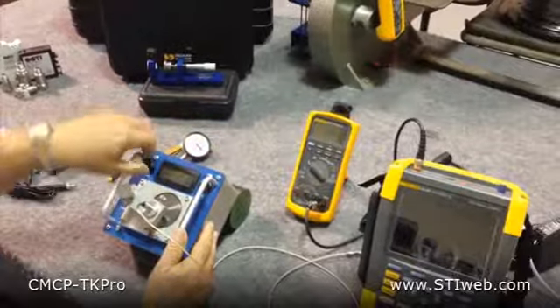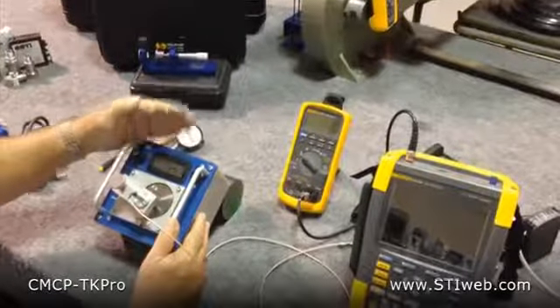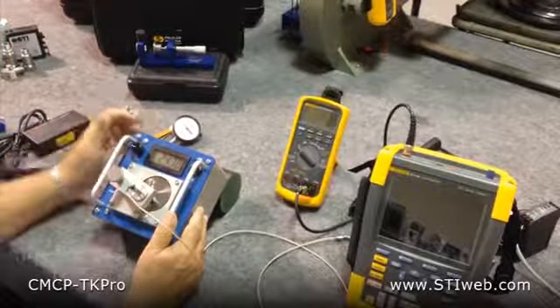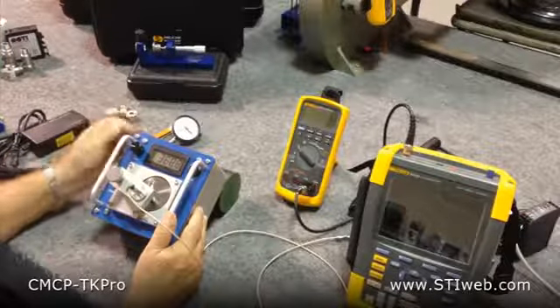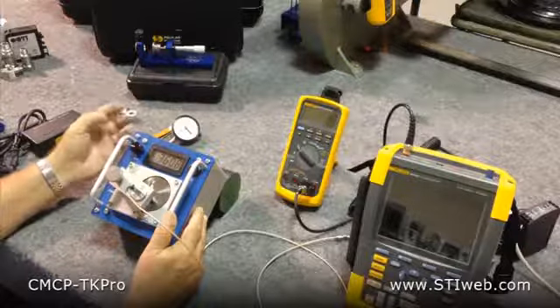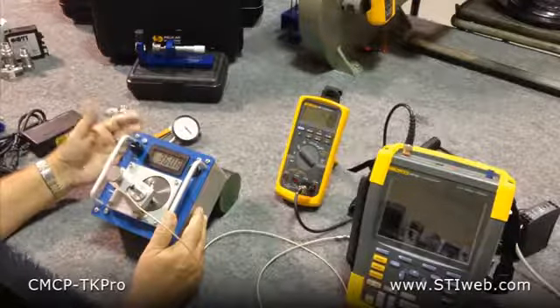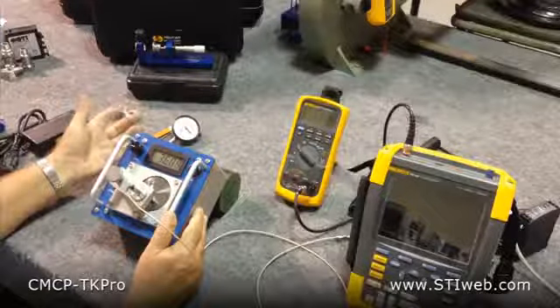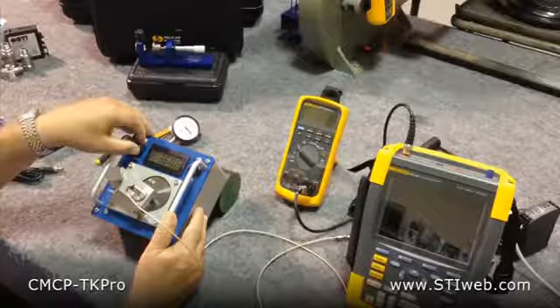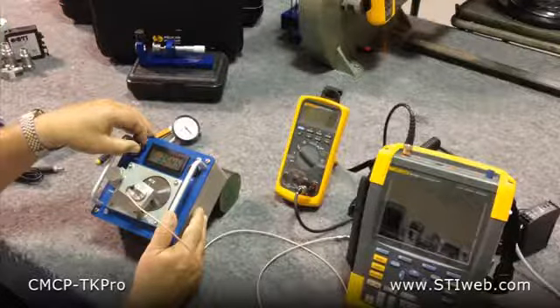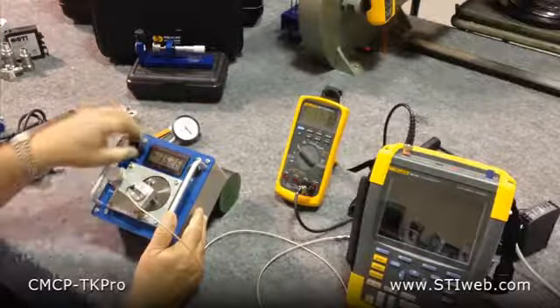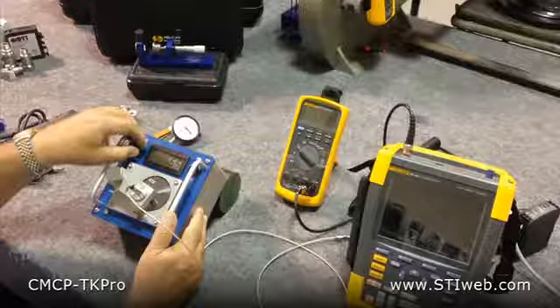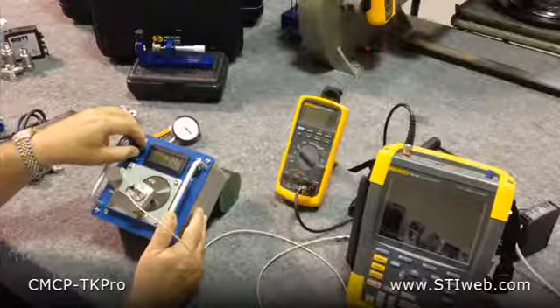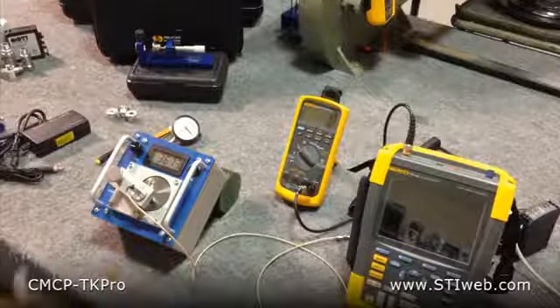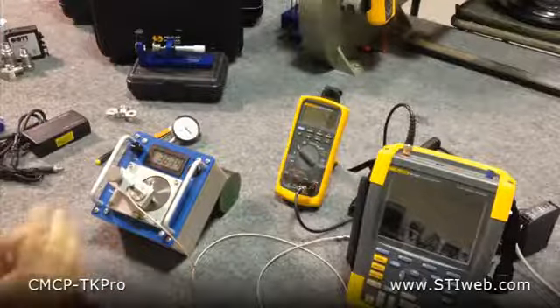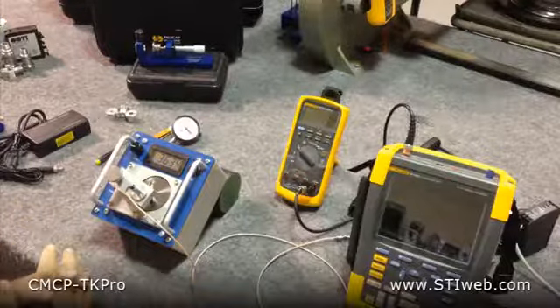We can turn the TKPro on, and you can see by looking at the tachometer we can adjust speed to be anything that we want it to be. Speed does not affect displacement. So basically the output of the proximity probe is going to be the same at 1 RPM as it's going to be at 7,000 RPM. But 3,600 RPM is very common. So we're going to run this at, you notice we have very excellent speed control, about 3,600 RPM, and it's at 11.52 volts DC minus gap.